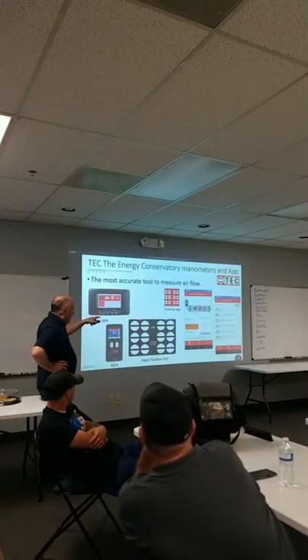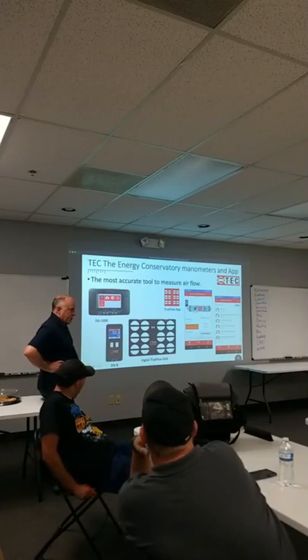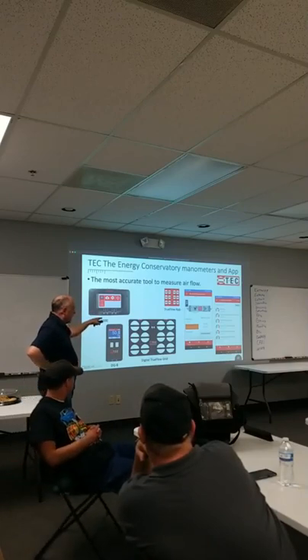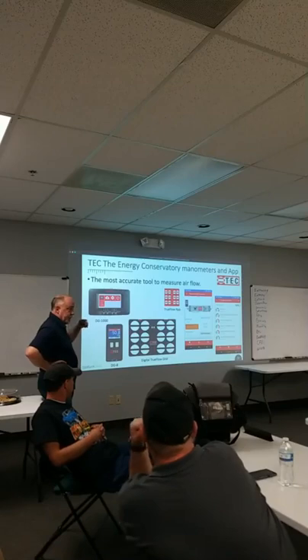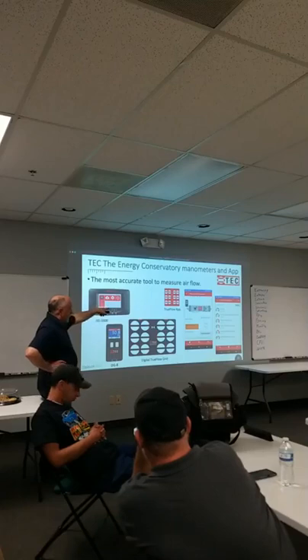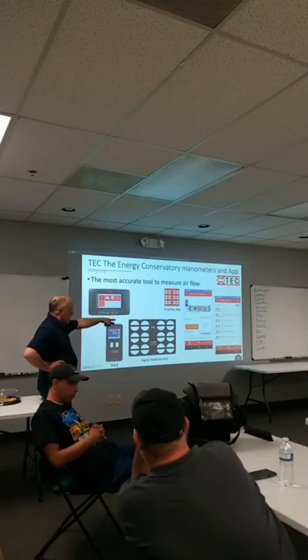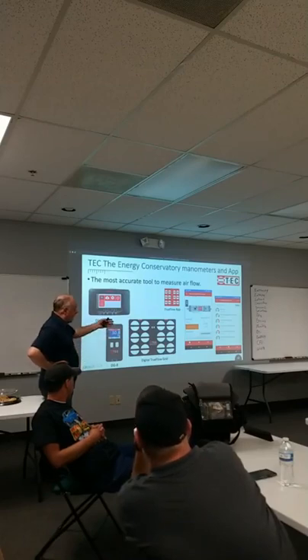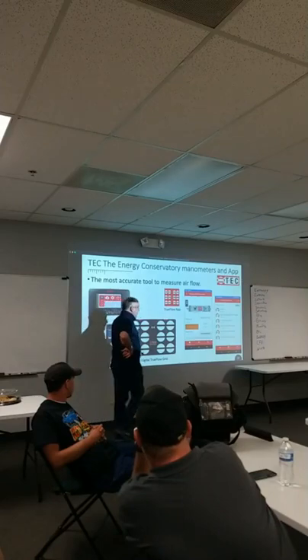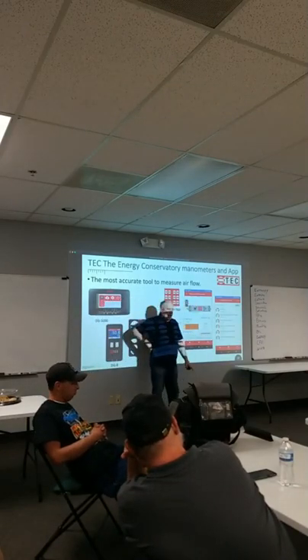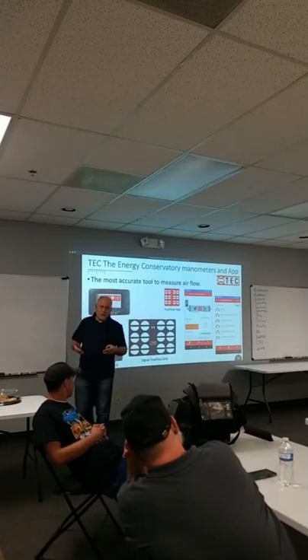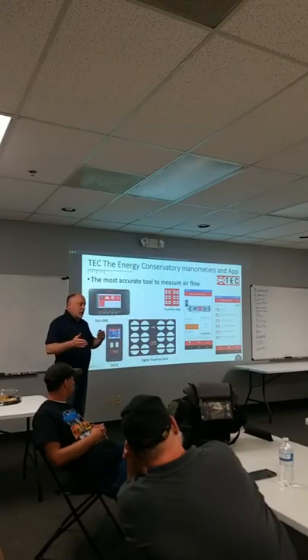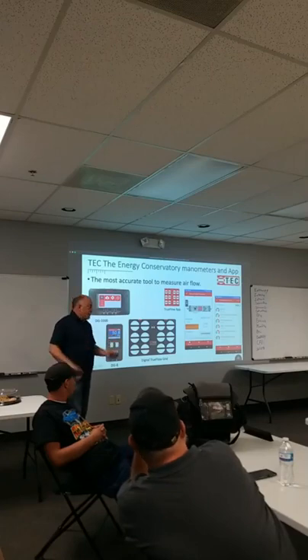Just recently, Energy Conservatory came out with a product called the Digital TrueFlow Grid. I don't know if you guys are aware of this, but it makes a volumetric measurement of airflow across a coil. So if you want to really dial in the airflow, the application not only makes the airflow measurement, but it also does your total external static pressure, your filter pressure drop, your coil pressure drop, supply pressure, and return pressure. Now, you go, well, why would we even want to measure that? Well, every one of these things has a target zone, right? So we're looking at all of these different pressure drops in a system. We have a static pressure budget we typically design for, and the software helps you analyze what part of the system you're having a problem at, so you can make the corrections.